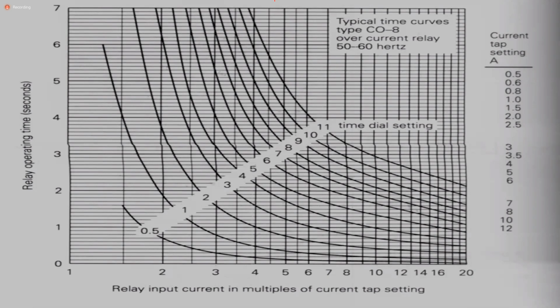No. What does the 8 represent? I'm happy that you're thinking. What does the 8 represent? The tap setting. What does that mean? That's the operating current, the current at which the relay operates. So if 5 amperes come, will the relay operate? No, sir. Good. So the relay will never operate. Everybody clear now? If 5 amperes is coming to the relay and the tap setting is 8, it means that with 5 amperes coming into the relay from the CT, the relay would never operate.